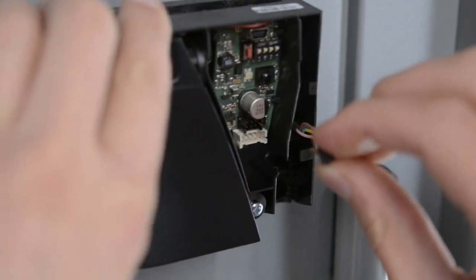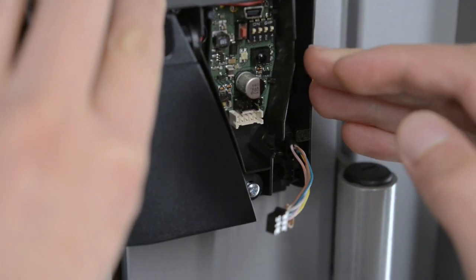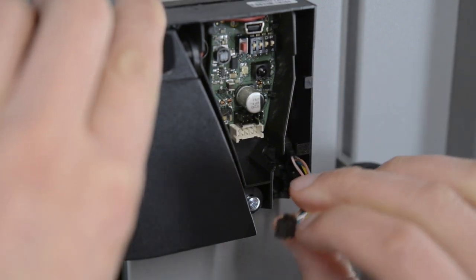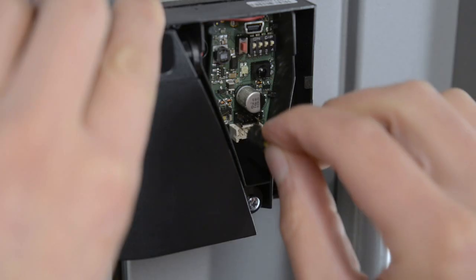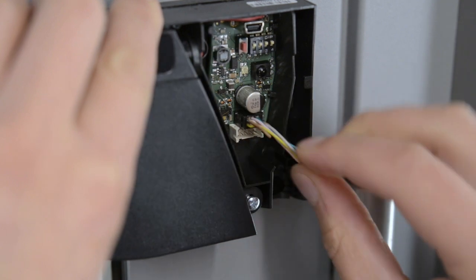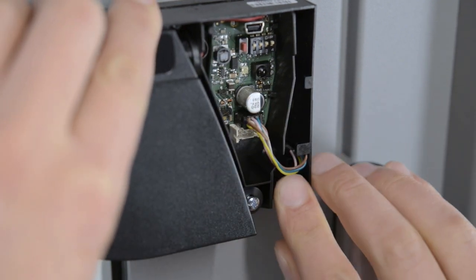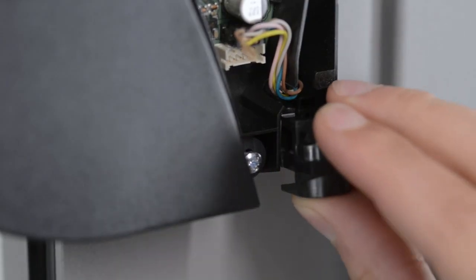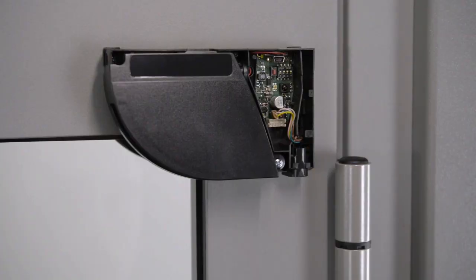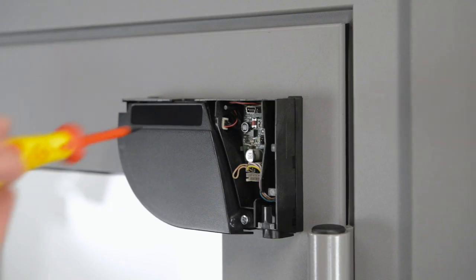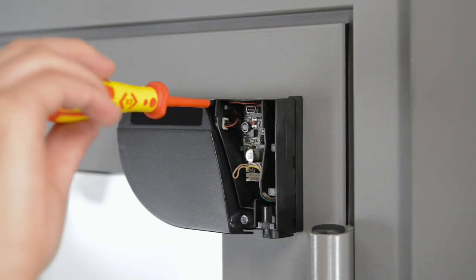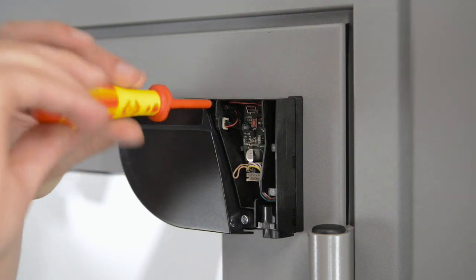On the door, pass the cable through the hole on the back of the sensor and connect it to the black connector. Make sure that all wires are safely tucked within the notch to avoid crushing them with the cover. Close the sensor, which will not be connected to the door controller, using a plug. Fasten the lock screw firmly in order to avoid vibrations during the door movement.